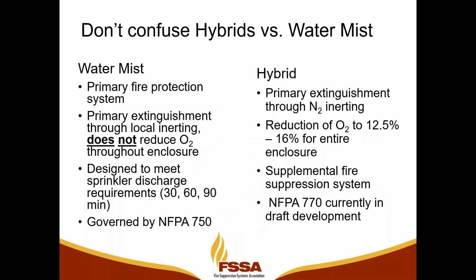So one thing I want to make sure we don't get confused about, because there seems to be some confusion in the marketplace, is hybrids versus water mist. They are two different systems. A water mist is not a hybrid, and a hybrid is not a water mist. So NFPA 750 governs water mist systems, whereas NFPA 770, which is currently in draft development, will govern hybrid type systems.